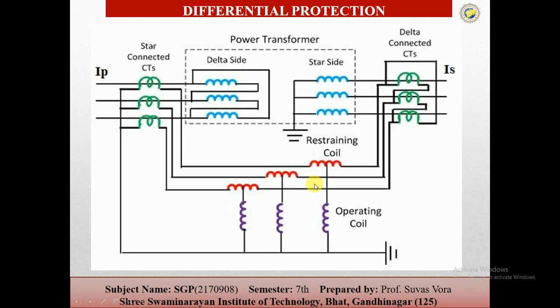It is connected to the operating coils. The restraining coil controls the sensitive characteristic of the relay. It restricts the unwanted tripping of the transformer due to imbalance current. That is, when the entering current IP is not equal to IS, at that time the relay works. The restraining coil also restrains the harmonics in the inrush current.